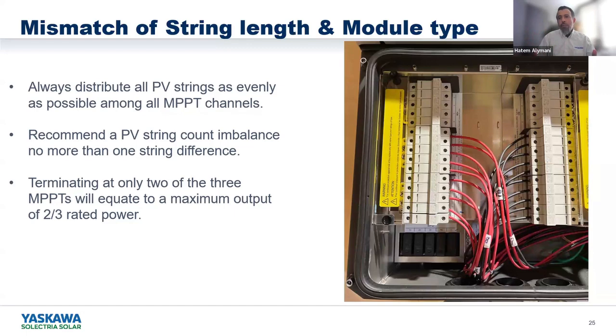Now, of course, they're not going to be equal. Most of the time, you're not going to be able to put 2, 2, 2 on each MPPT. So what we also recommend is to try as much as possible to limit the difference in the number of strings per MPPT to 1. So let's say 3, 3, 2 or 3, 2, 2. Not more than one string of difference between all the MBBTs. So those are basically the two major questions that we get from our customers and our end users.